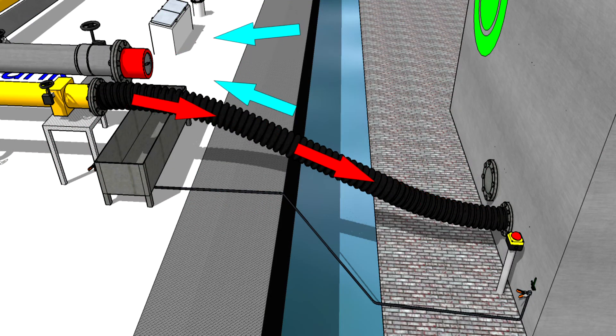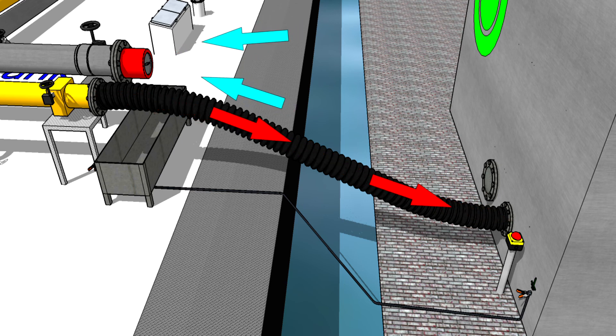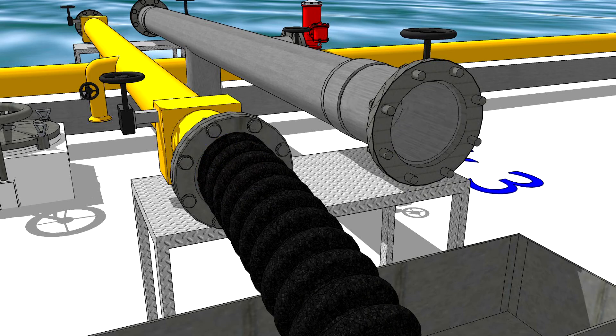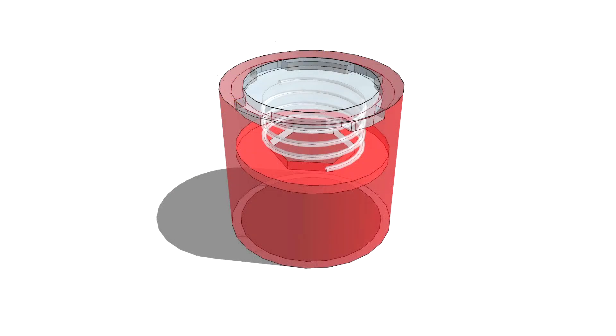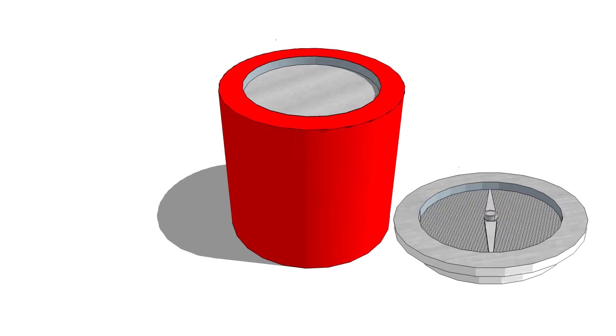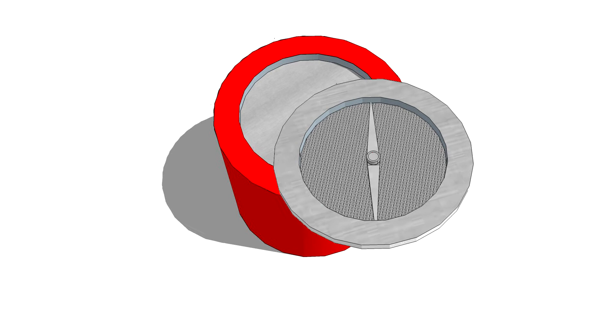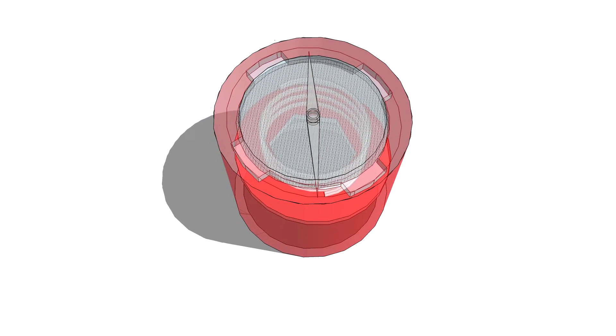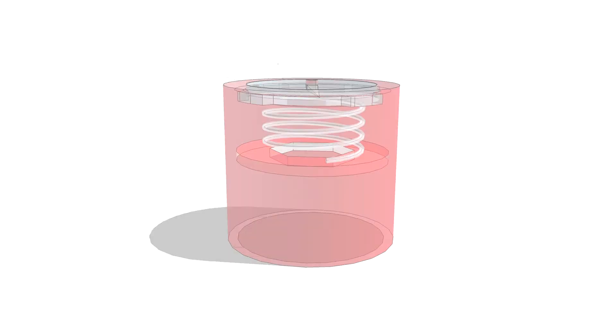Most reception facilities work with suction of clean air from the atmosphere. In order to prevent any open connections to the atmosphere, the Informal Working Group proposes to require a spring-loaded low pressure valve on the piping. This spring-loaded low pressure valve shall be equipped with an appropriate flame arrester if explosion protection is required in Table C, Column 17.